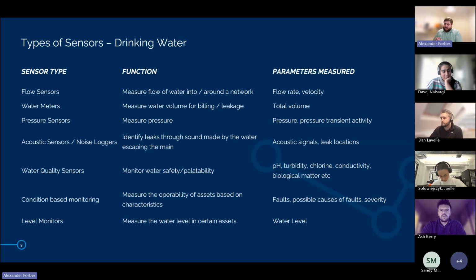We've got some water quality sensors there - that's a really big one. As an example, we put chlorine monitors on the outlet of water treatment works to make sure we're not overdosing chlorine, to make sure we're not putting anyone at harm's way, and to make sure the water is of a good enough quality to actually send out to the customers.